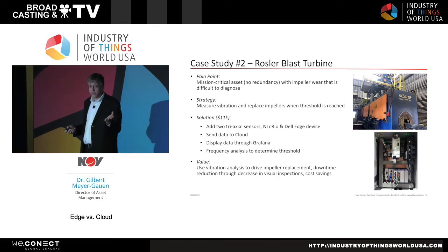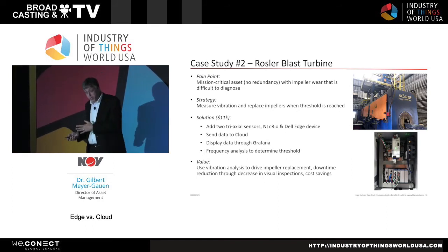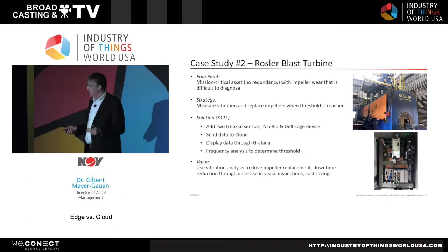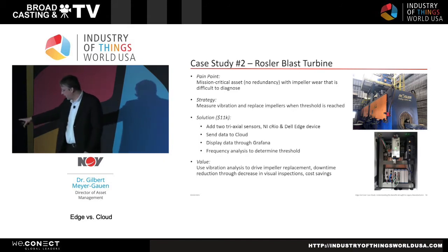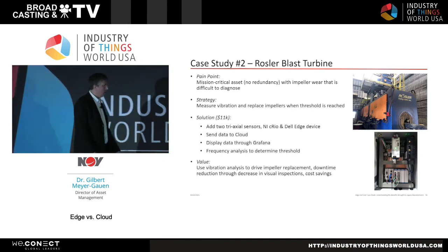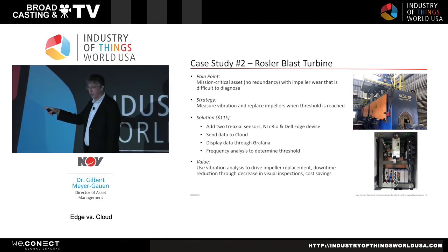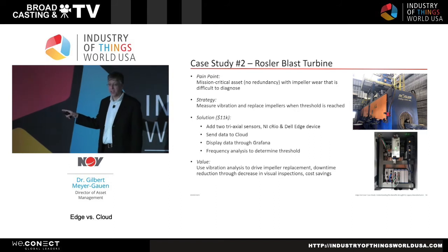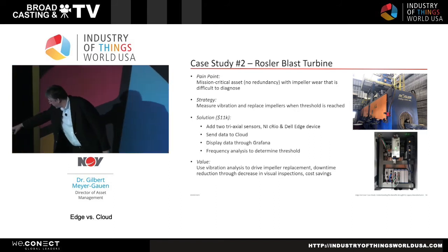So you have one accelerometer, that's like 30,000 readings per second. Now, we don't do it at that rate. We use 6,500 up to 10,000, but you know, we also have solutions where they use 20,000 hertz. But for this, you cannot use the CRIO any longer. You have to go to the crazy Danes. They have a company called Brüel and Kjær, where the device costs like, I don't even know, 9 or 10 grand. So this is the data acquisition device.